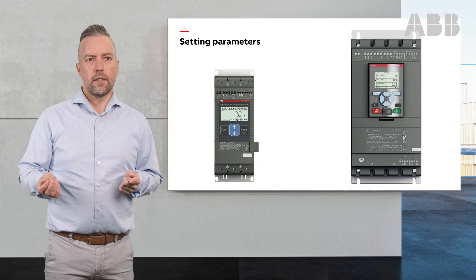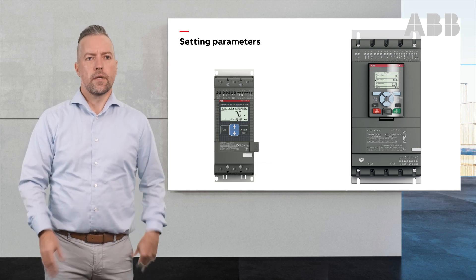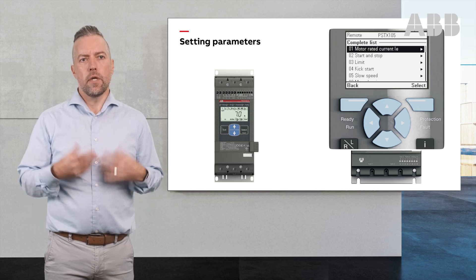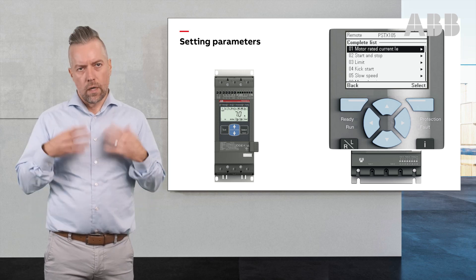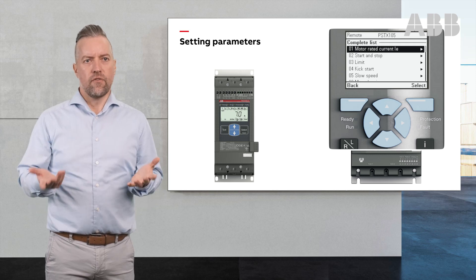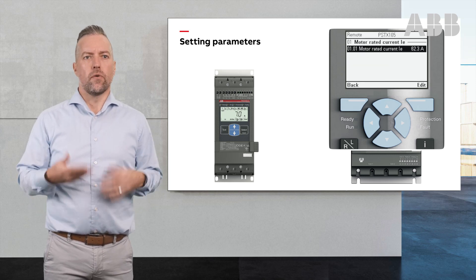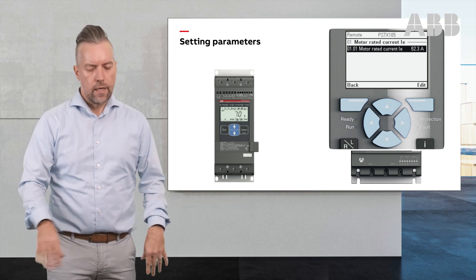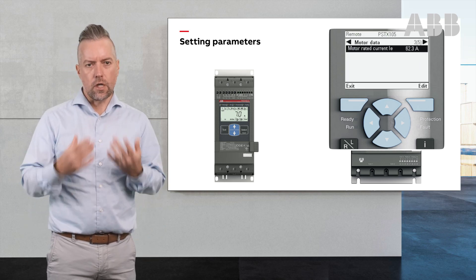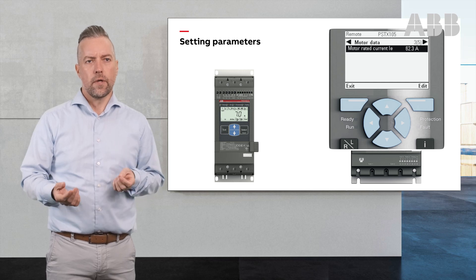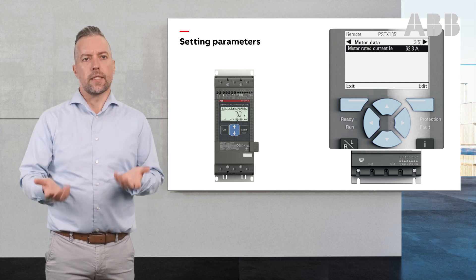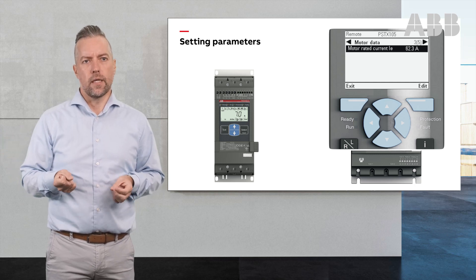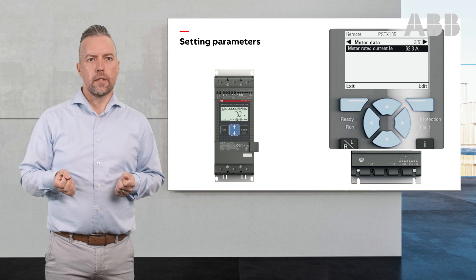For the PSTX you actually have two ways to do it. Either you go into menu, parameters, all parameters, and then the first one that comes up is the motor rated current that you select and change. You also get the option when you start up the soft starter — when you power up, you get to the basic setup, and there you will also have the possibility to set the motor rated current directly.